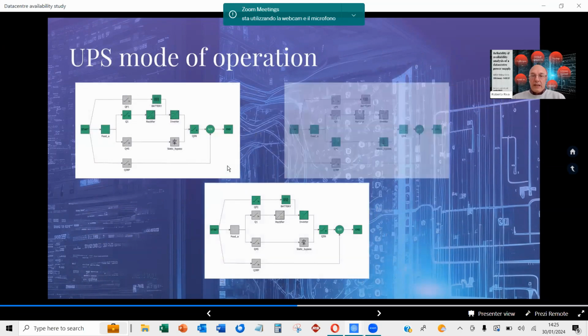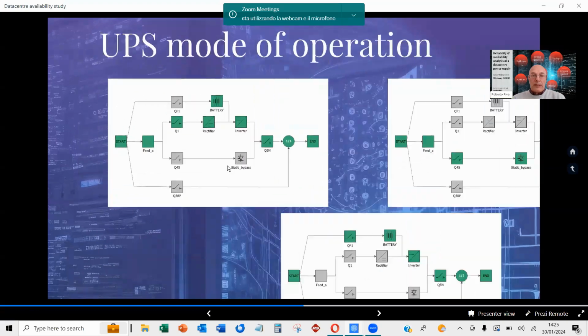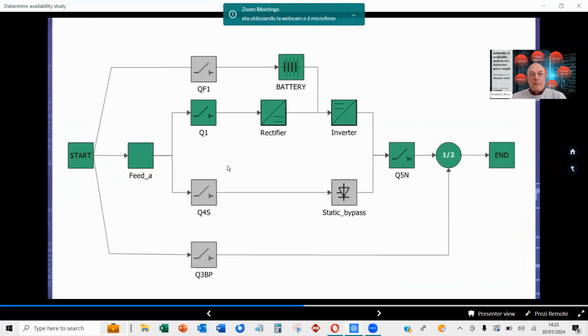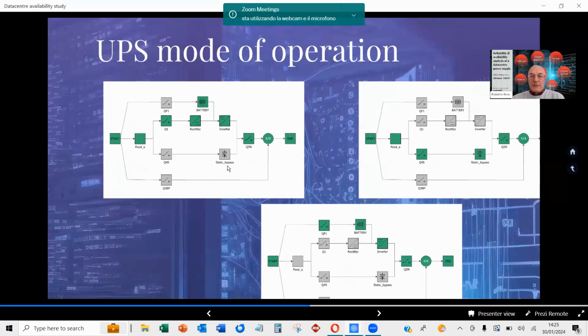So here we have a very simple schematic of the UPS mode of operation. We represented the sequence in green from start to end. In normal operation, we go through the rectifier, inverter, some circuit breakers and so on, while at the same time recharging the battery. That's the normal operation of the UPS.